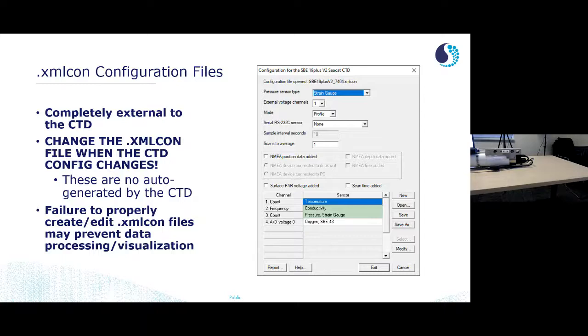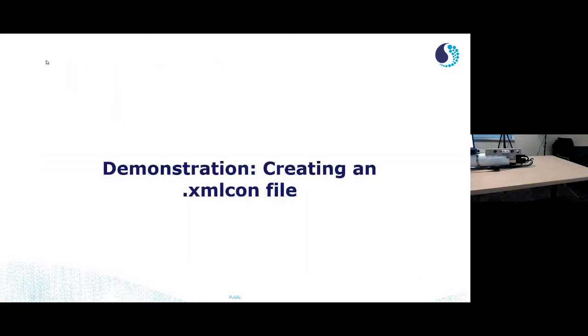That's the best case scenario. Or B, actually process your data with incorrect calibration coefficients. And you might not notice. The changes will be subtle, but they will be incorrect data. So it's very important that you modify your calibration, or I'm sorry, your configuration file to reflect the instrument's proper calibration. Okay, so we're going to take a quick look at that.